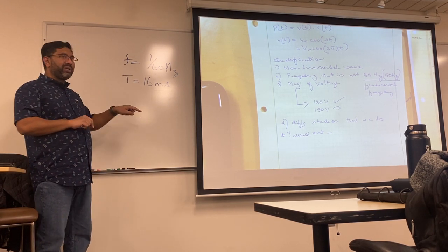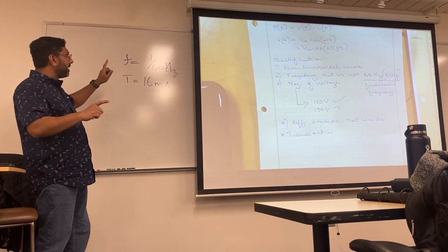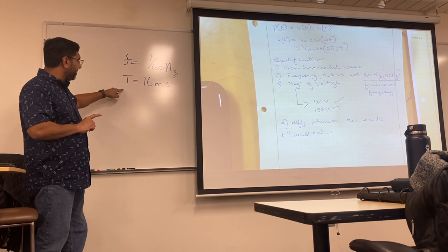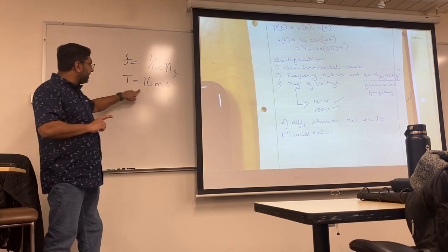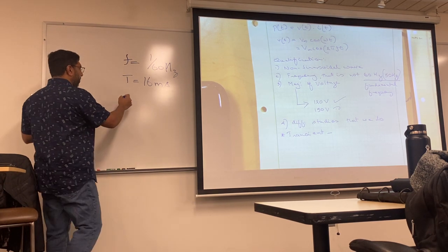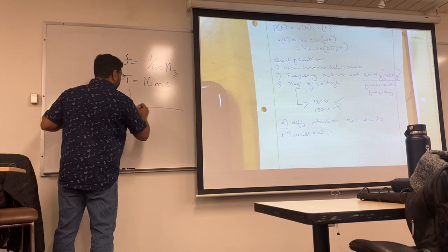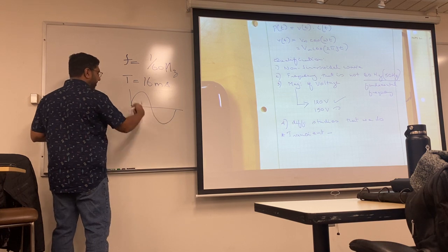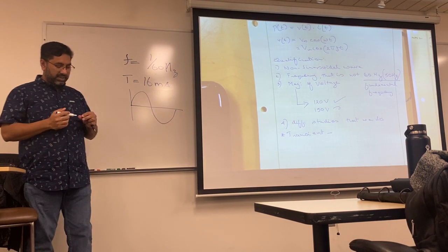So using atomic clock, we are talking to different substations and figuring out which breaker to open, what needs to happen at what time period and what not. But 16 milliseconds, keep this in mind. That's literally your one cycle. So the time it takes for one VFT or IFT to go through, it's 16 milliseconds.